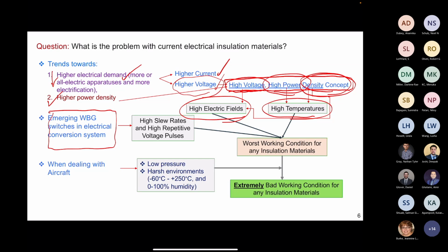If you see it from the insulation side, frequency and slew rate are the two most critical factors of a voltage pulse that influence the level of degradation of insulation exposed to such voltages. If you combine these three factors, high slew rates, high repetitive voltage, and high electric field, along with high temperature, you get a very bad working condition for any insulation material.